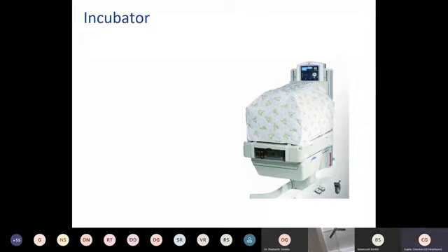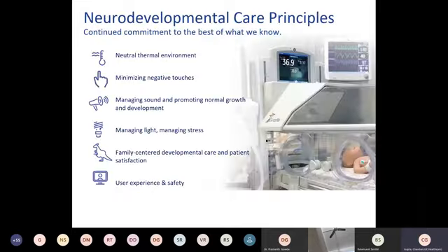The next product is the incubator. Whenever you are deciding on a closed care system incubator, in India, approximately 5% of the beds today are using incubators. The first thing, whenever you are talking about incubators, people use incubators for the most fragile babies. So the babies which are, let's say, less than 30 weeks, people use incubators. So you can understand that the weight will be less than 1000 grams. So it's very important that we take care of the various things. So we will talk about that.